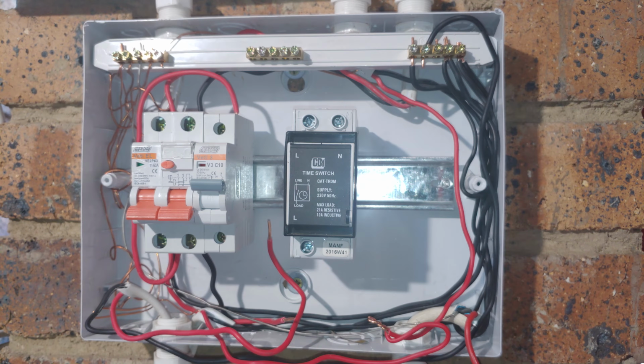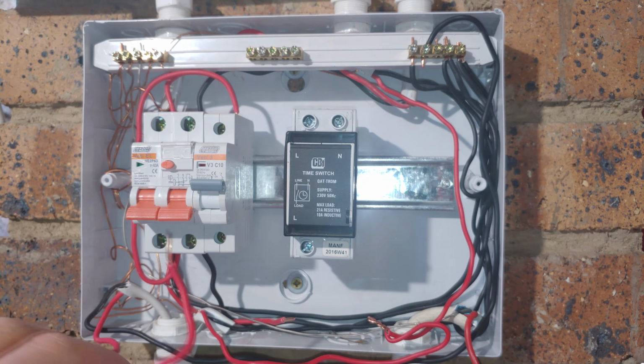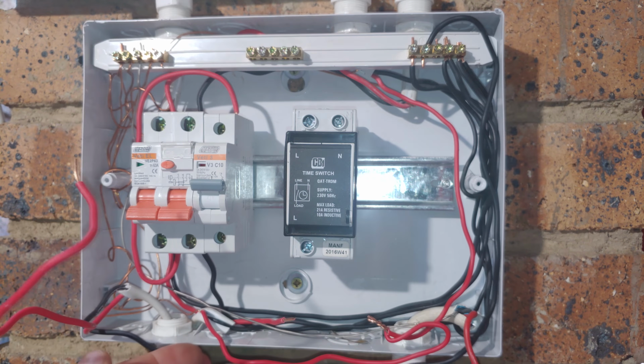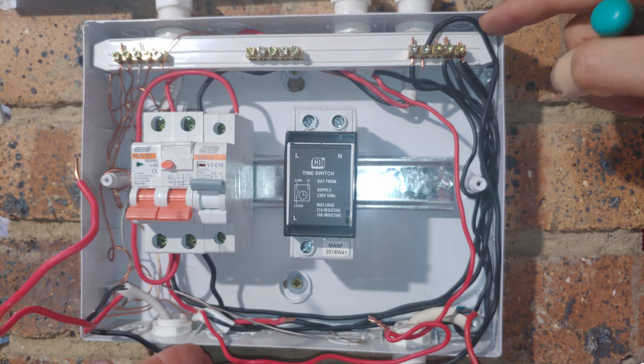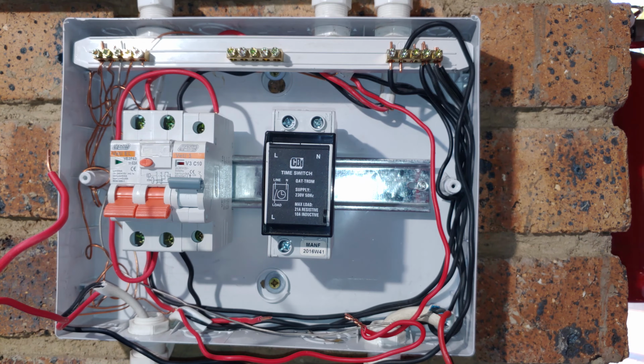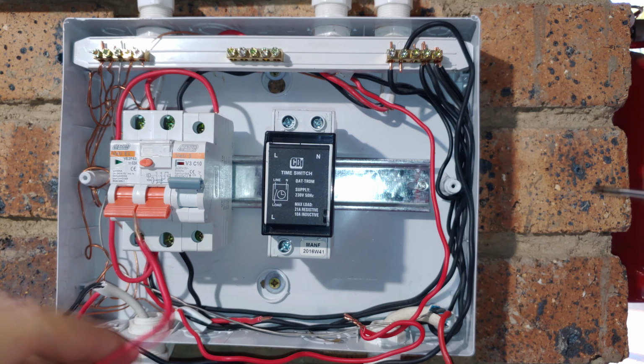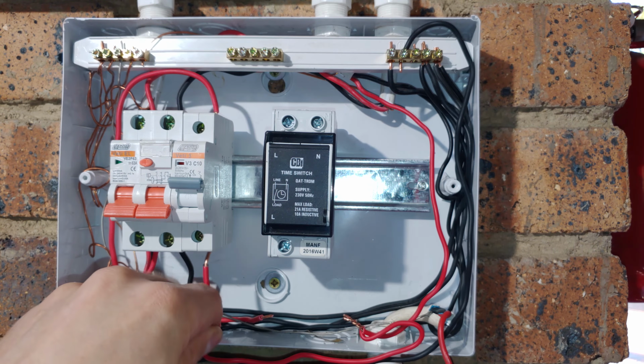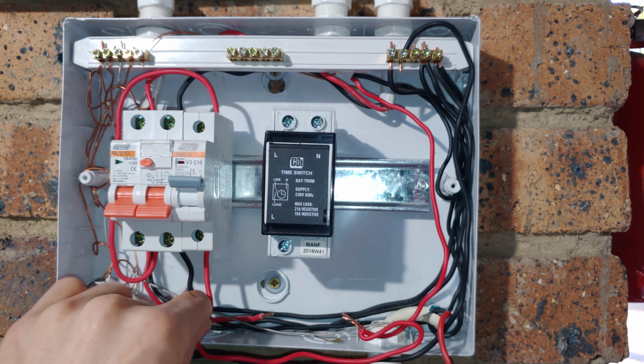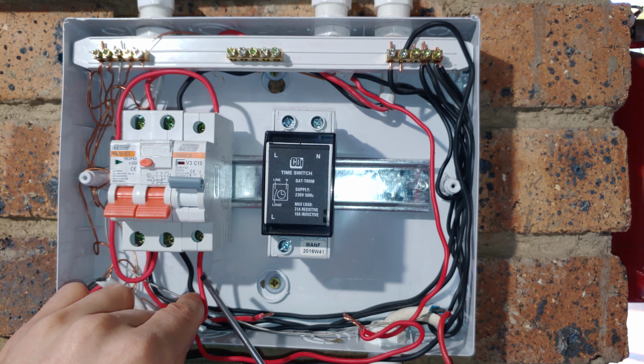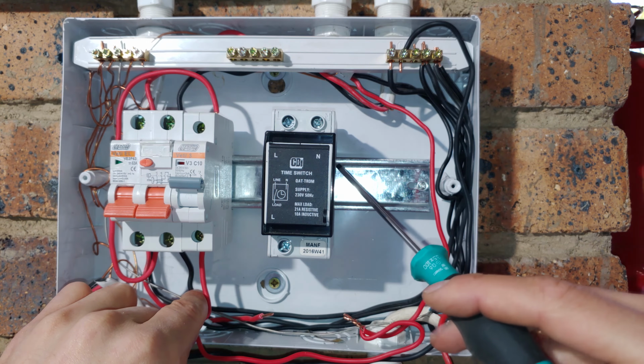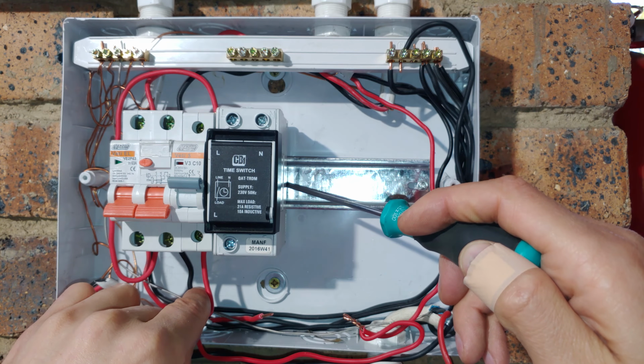Now the first thing you'd want to do is locate the circuit that you're trying to control. Now in this case, here it is. This happens to be the pool pump, and there is the neutral. The neutral is already connected to the neutral bar. So all that needs to happen now is the live, which is in your case probably connected to the circuit breaker already, needs to be disconnected from the circuit breaker and allow this switch to come into play.